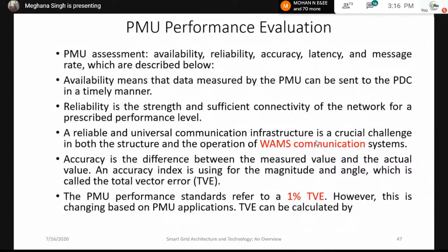This is changing based on PMU applications. The concepts related to message rate resolution: the PMU takes rapid physical measurements, either voltage or current, then does time stamping, and reports the phasor for each cycle or 2 cycles. The reporting phase rate is expressed in frames per second.